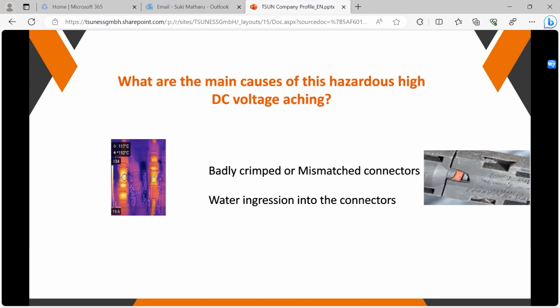Crimping on site is a big issue. Mismatches are a big issue, as you can see from that little thermal image. An eye won't be able to see that there's a hotspot there and a hotspot higher. So, for example, if you suddenly get 800 volts or 600 volts DC going through that, which could easily happen in a commercial site, that could become a problematic issue. So we need to avoid that wherever possible.